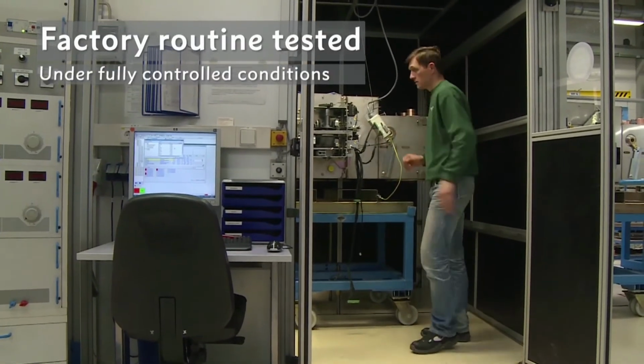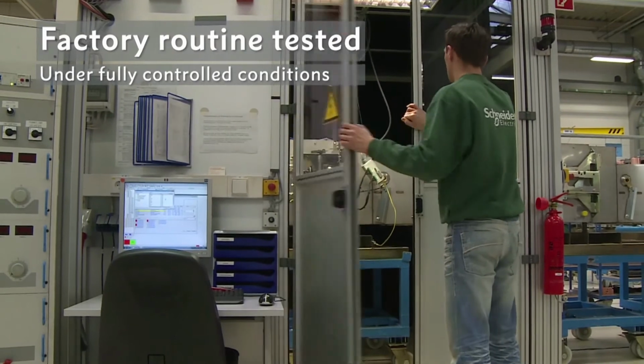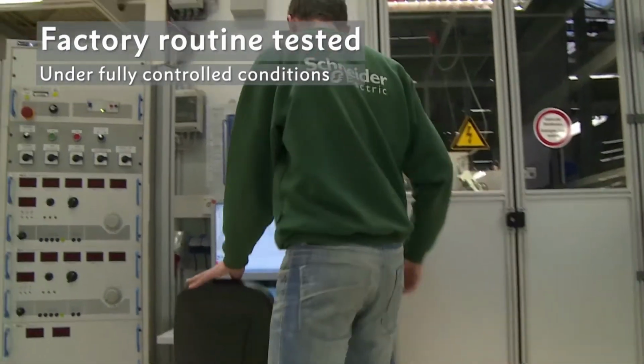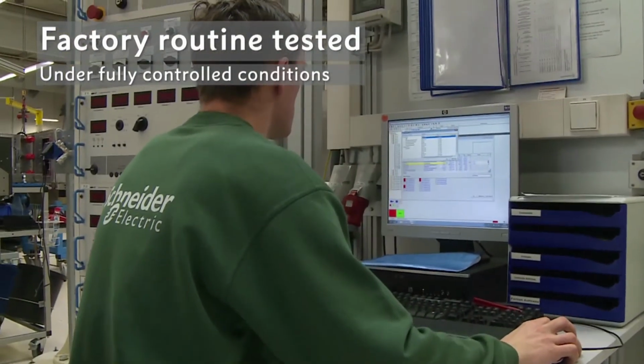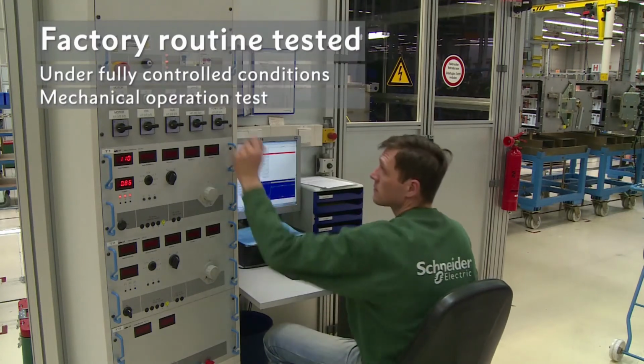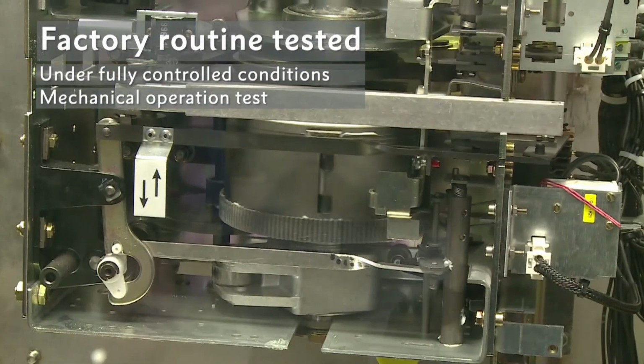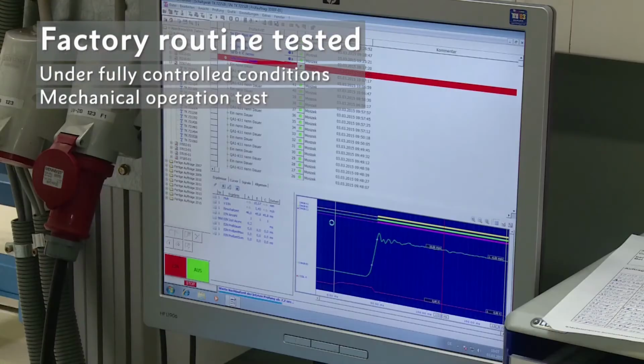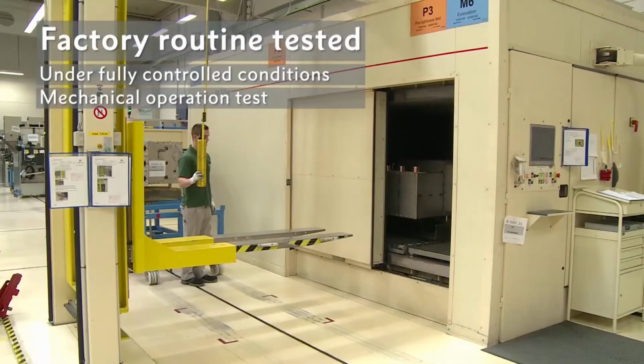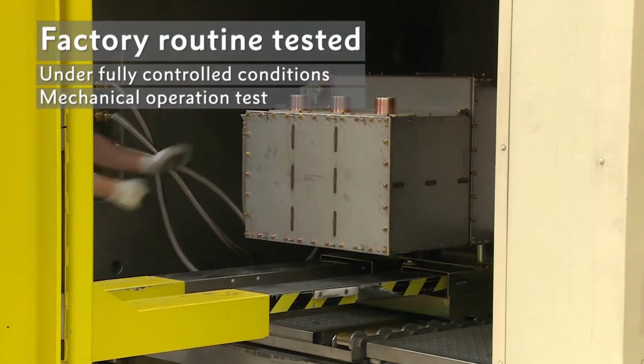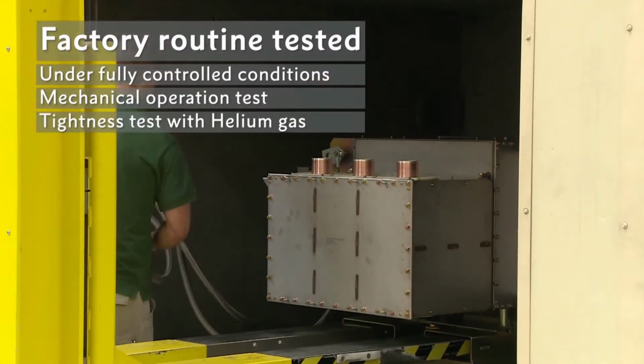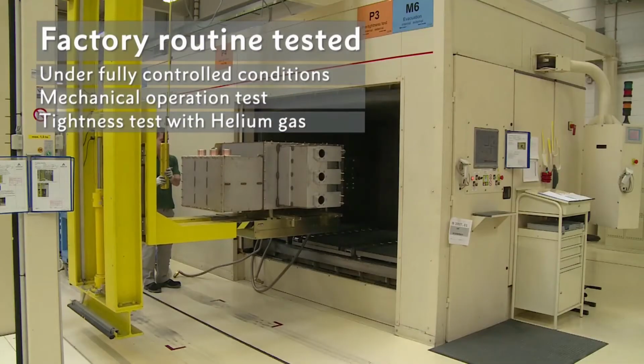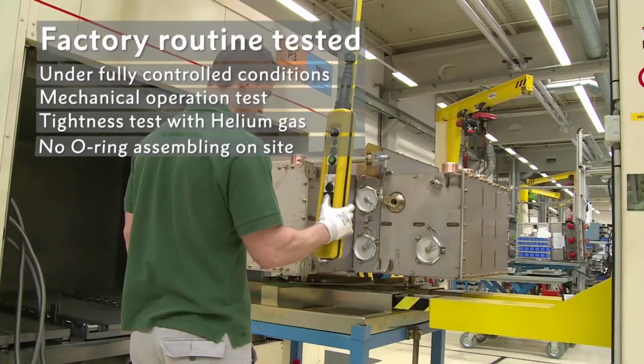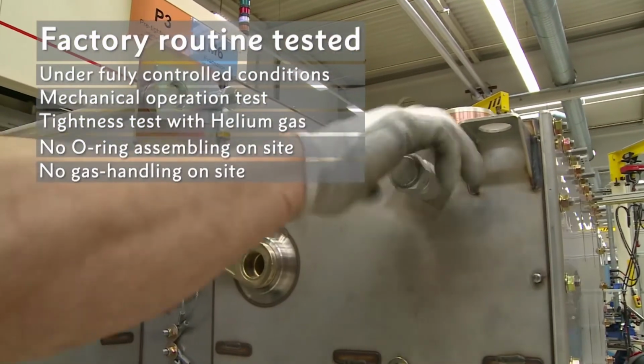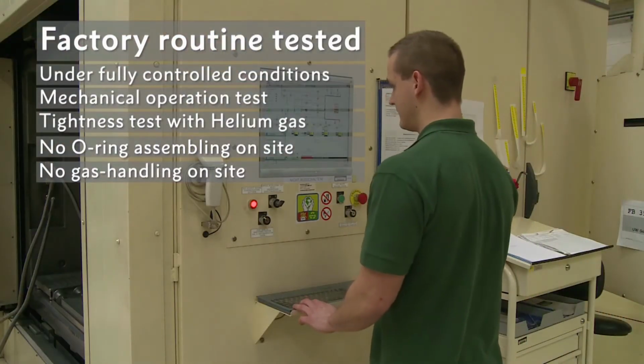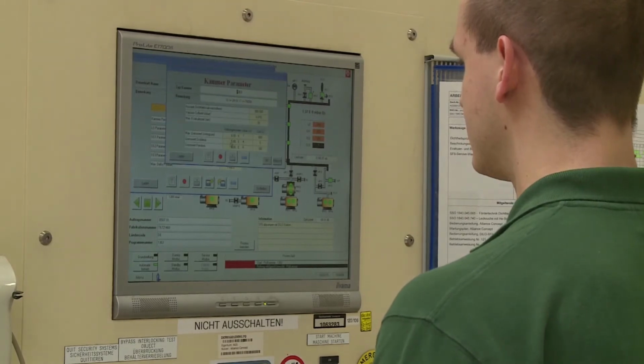Routine tests are carried out under fully controlled environmental conditions in all Schneider Electric facilities producing GHA switchgear, and recorded automatically as an integral part of the production process. The first routine test before closing the tank is the mechanical operation test of the circuit breaker mechanism for close and trip speed, closing and opening times, and synchronicity of phases for related switching cycles. After closing the gas tank for its operational life, the tank is leakage tested and filled with SF6 gas in the factory. All methods throughout the process are controlled automatically, with the advantage of no O-ring assembly on site. The leakage test is carried out using helium gas to secure tightness safety and fulfill the IEC standard leakage rate requirements for sealed pressure systems.